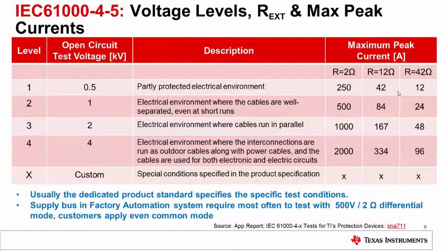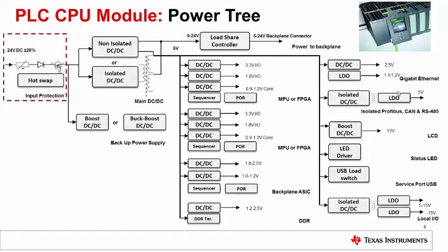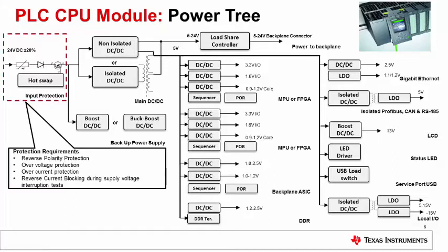The dedicated product standard specifies the specific test conditions. A typical supply bus in factory automation and control requires at least 500 V, 2 ohm surge compliance. As an example, consider a PLC CPU module powered from an external field power supply. This is the power tree of the end equipment, and because it is powered from an external supply, input protection is required.